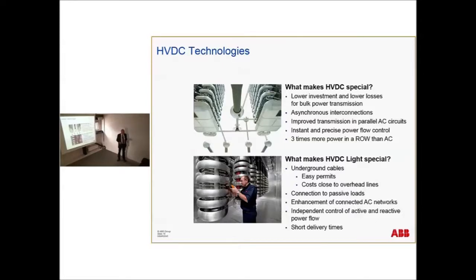compared with an AC transmission. Then the new technology, HVDC Light. On top of this, we can have these extruded light cables, which are very suitable also for underground cables instead of overhead lines. And you can combine them with overhead lines if you want. You can connect to passive loads. That means that you can have radial feeding, an island, an oil and gas platform, or whatever. And you can control the active and reactive power independently.